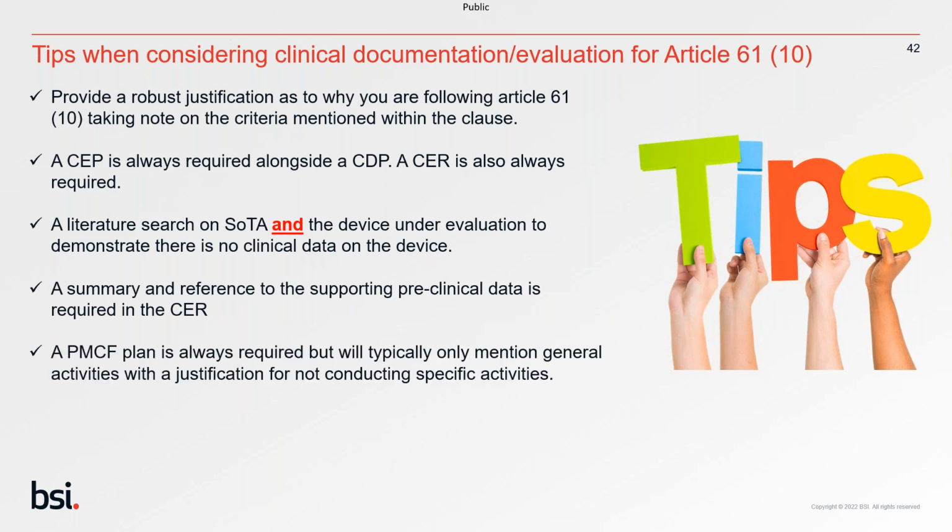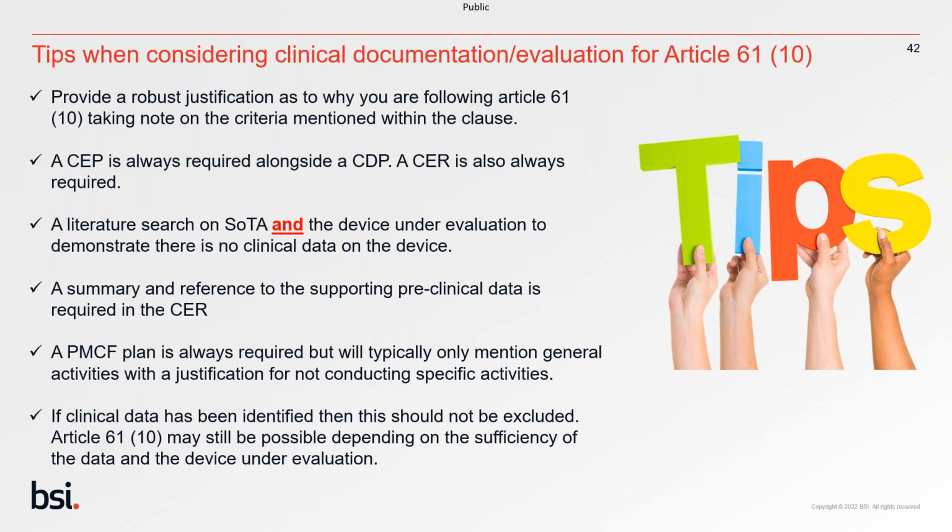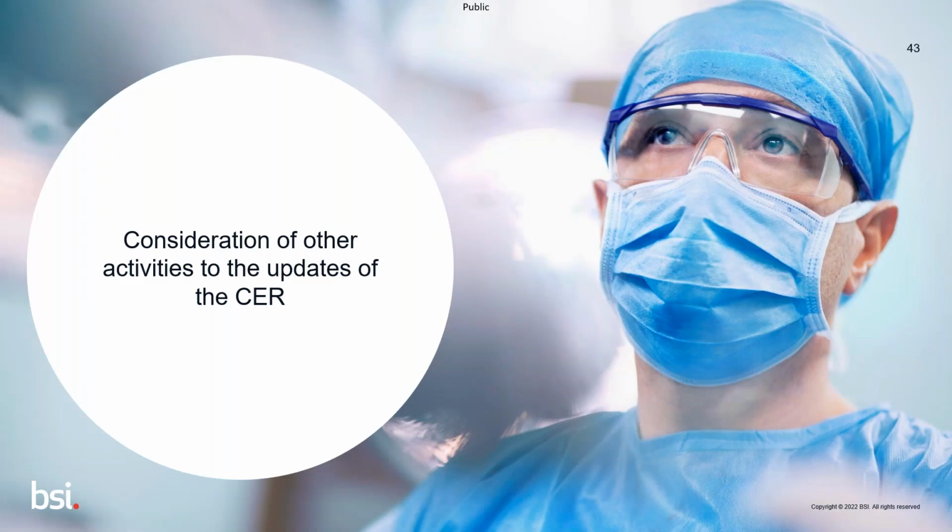And also a PMCF plan is always required, but will typically only mention general activities with a justification for not conducting specific activities. And if clinical data has been identified, do not exclude it. Just mention that you've considered it and what its sufficiency is, or where there is a lack of sufficiency to be able to use that data to meet the GSPRs.